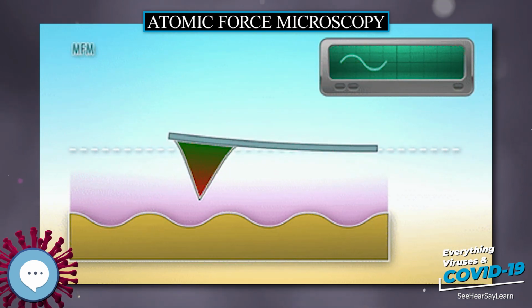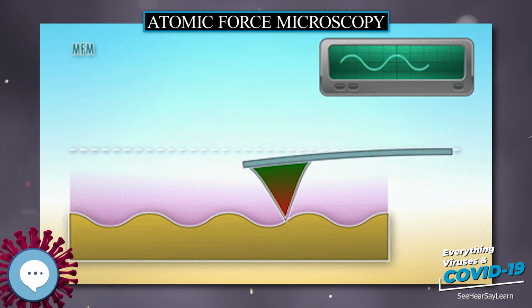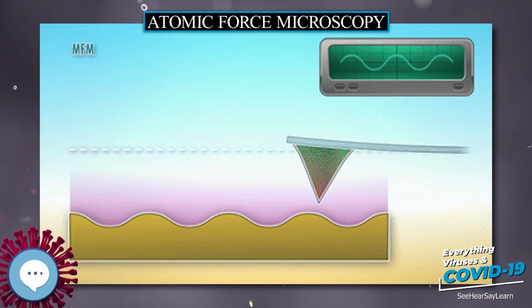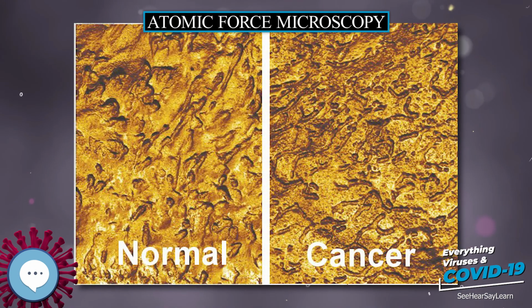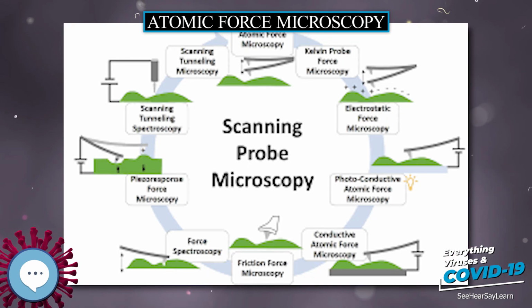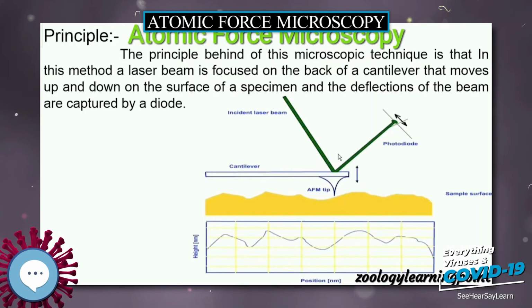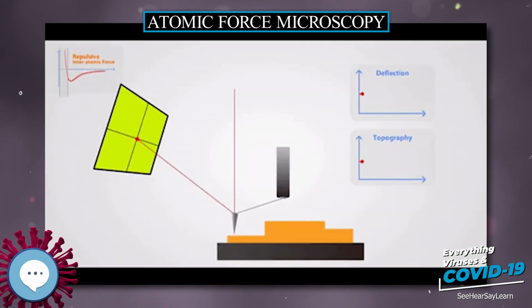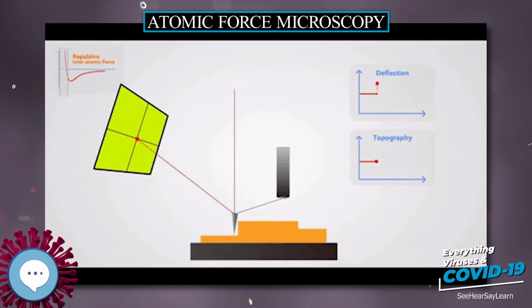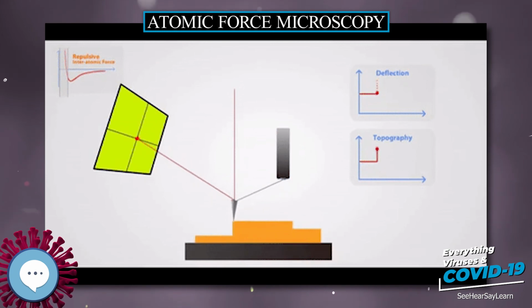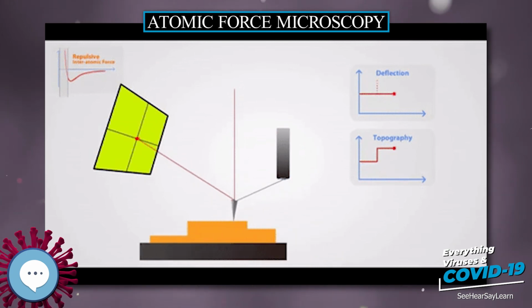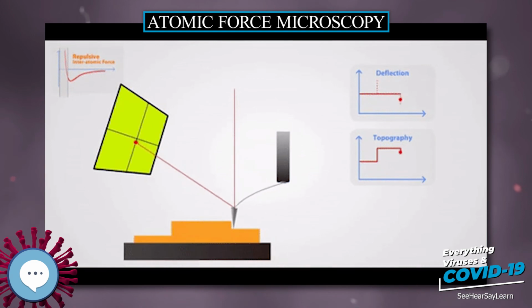The interaction of forces acting on the cantilever when the tip comes close to the surface, van der Waals forces, dipole-dipole interactions, electrostatic forces, etc., cause the amplitude of the cantilever's oscillation to change, usually decrease, as the tip gets closer to the sample. This amplitude is used as the parameter that goes into the electronic servo that controls the height of the cantilever above the sample. The servo adjusts the height to maintain a set cantilever oscillation amplitude as the cantilever is scanned over the sample.